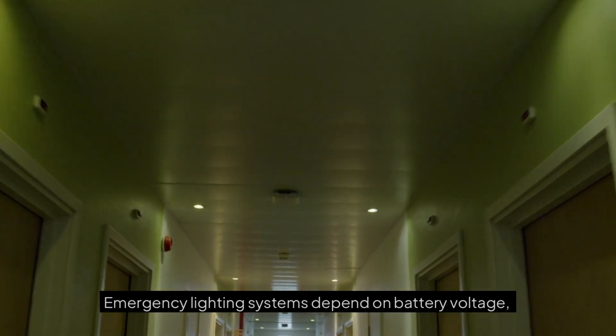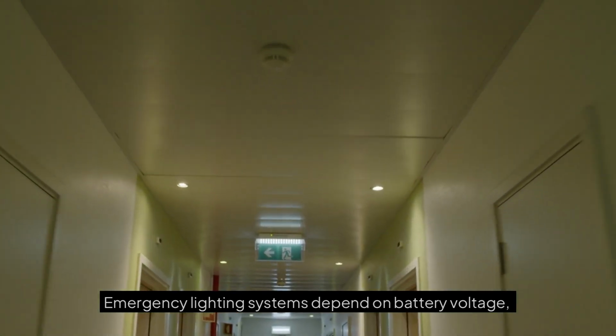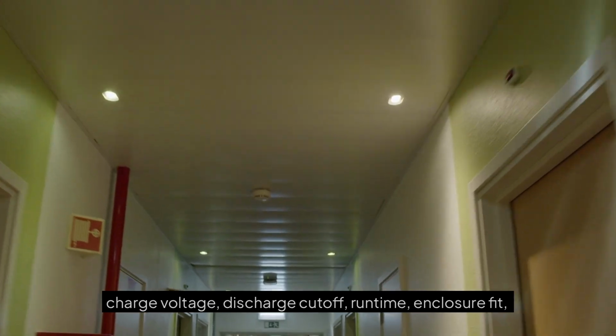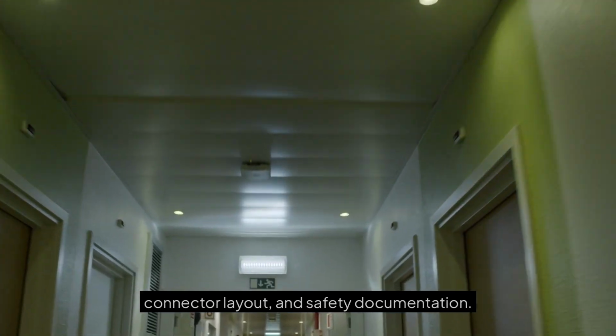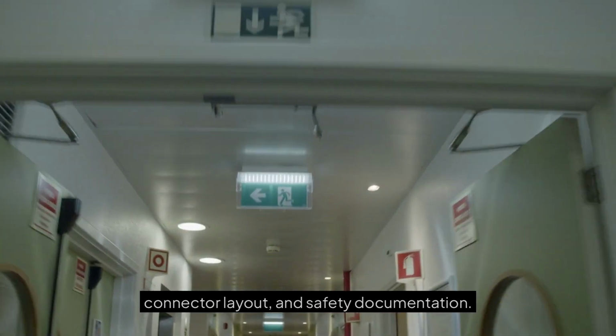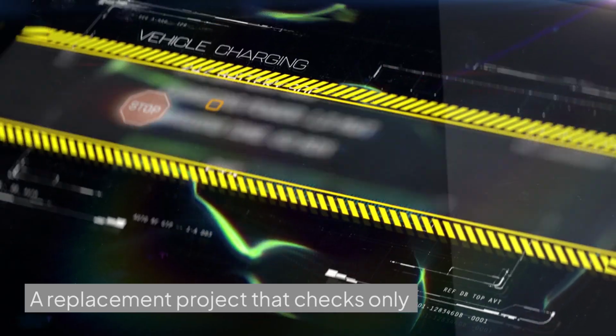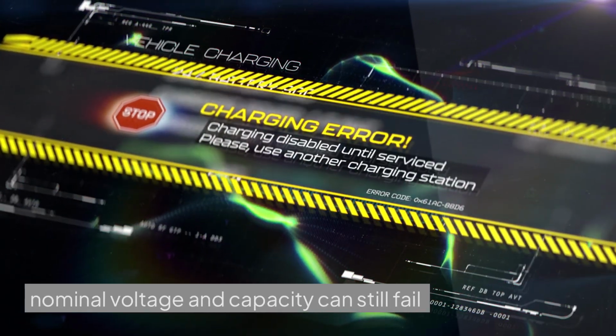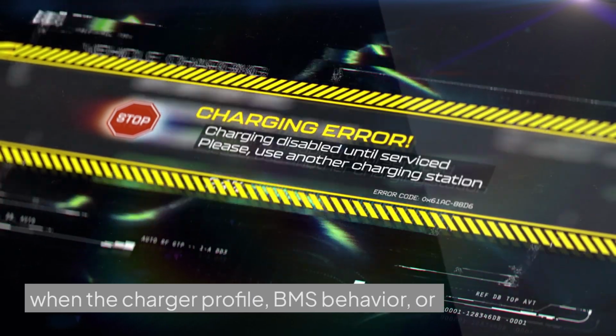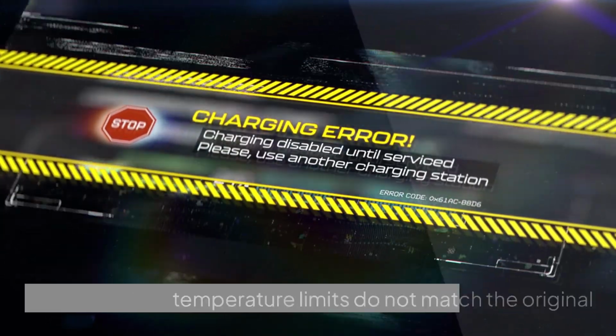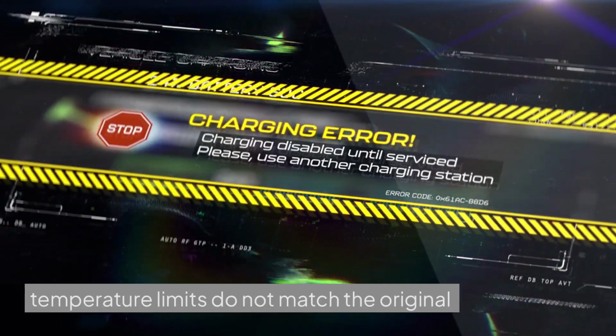Emergency lighting systems depend on battery voltage, charge voltage, discharge cutoff, runtime, enclosure fit, connector layout, and safety documentation. A replacement project that checks only nominal voltage and capacity can still fail when the charger profile, BMS behavior, or temperature limits do not match the original system.